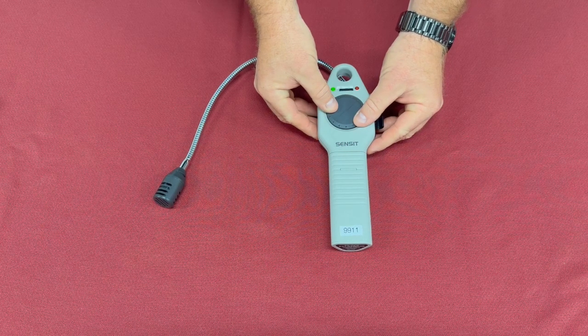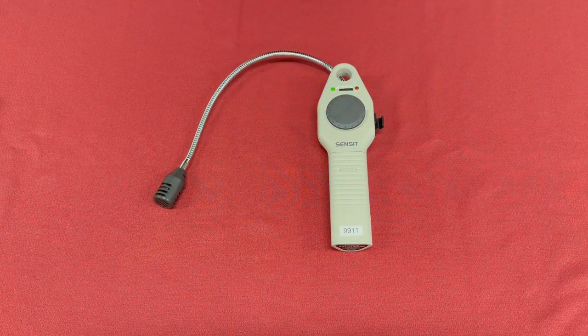And then you can take this instrument down a gas line or to an appliance and see if that appliance is actually leaking. When you get in the area of the leak, it's kind of like using the hot-cold system, as you get closer to the leak, it's going to start clicking faster. And you can actually trace it right down to where the leak's at, usually in a coupling or something like that, allowing you to turn that appliance off, not turning off the gas to the entire structure. It's powered by a 9-volt battery. It just needs to be changed if it's dead. Besides that, there's no calibration or maintenance with this piece of equipment.